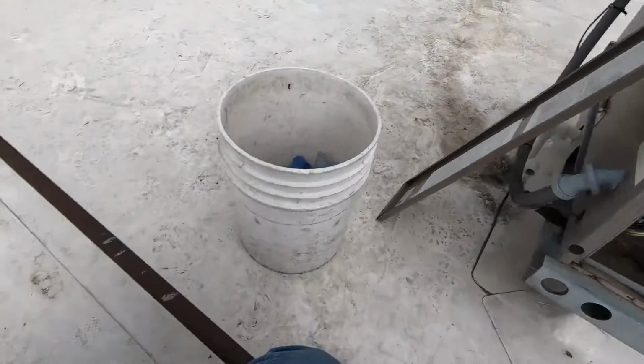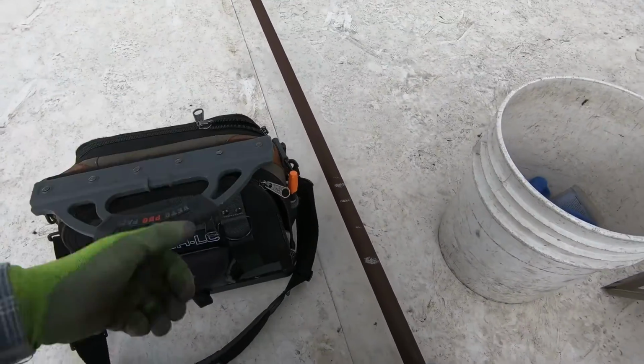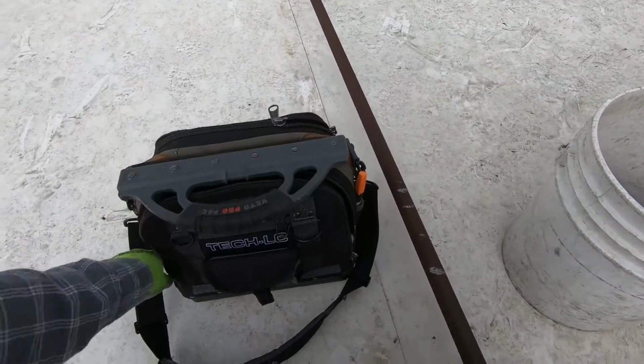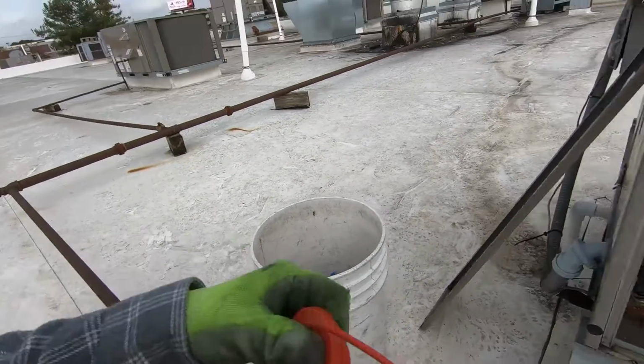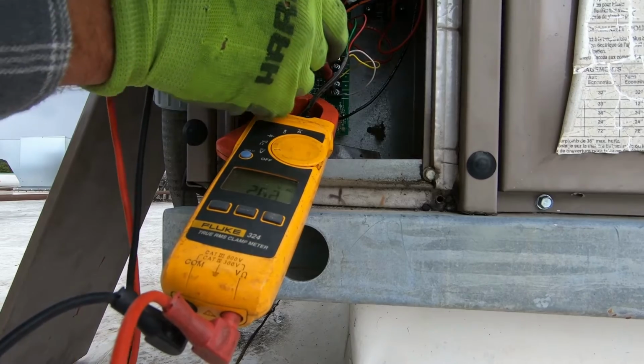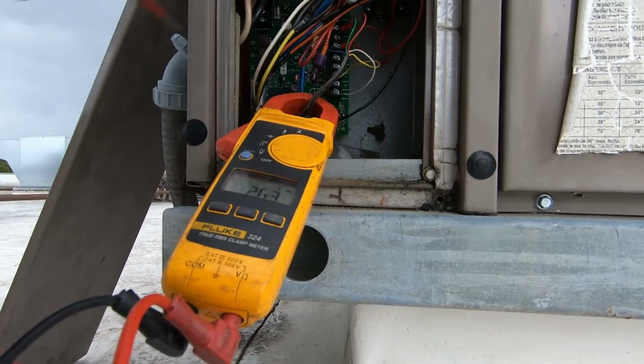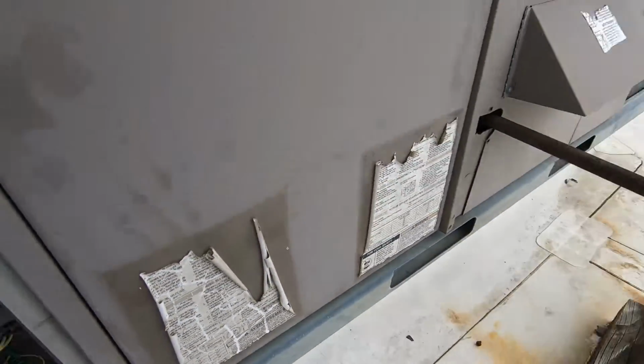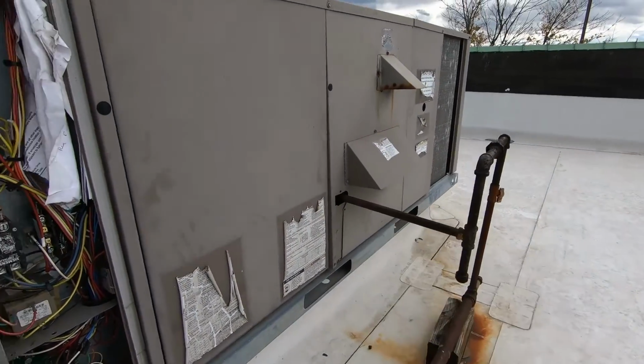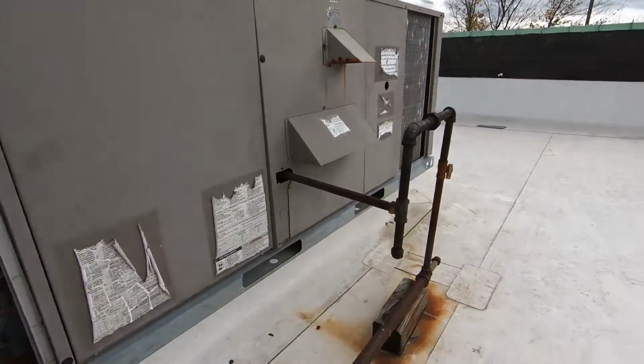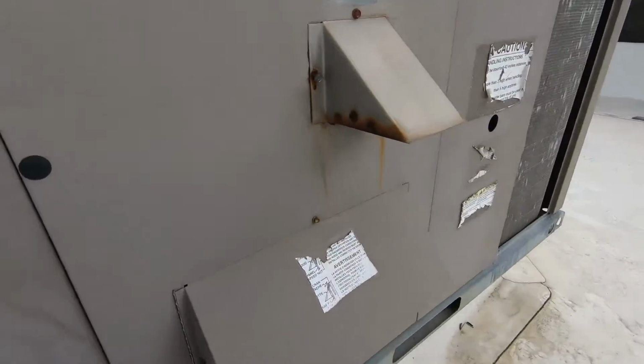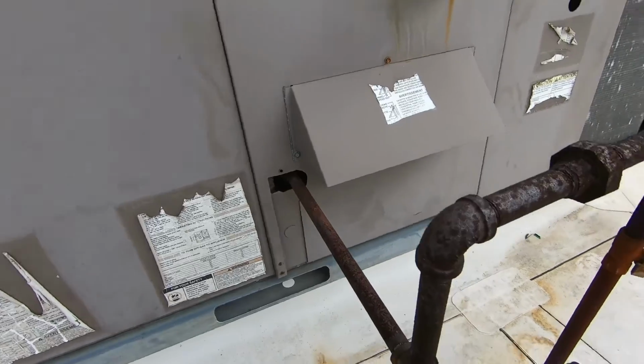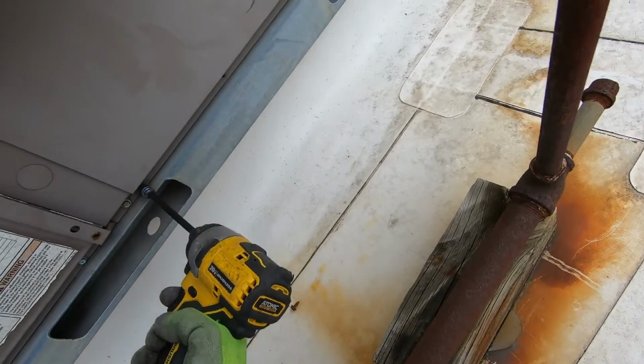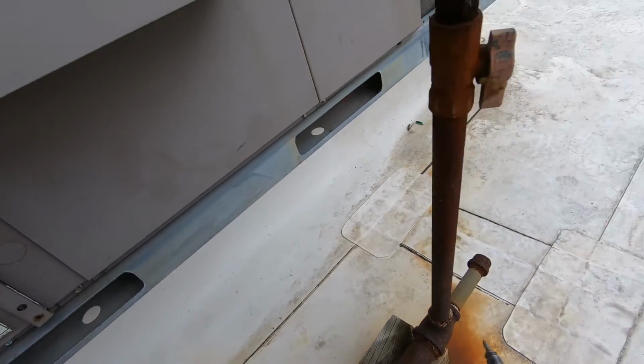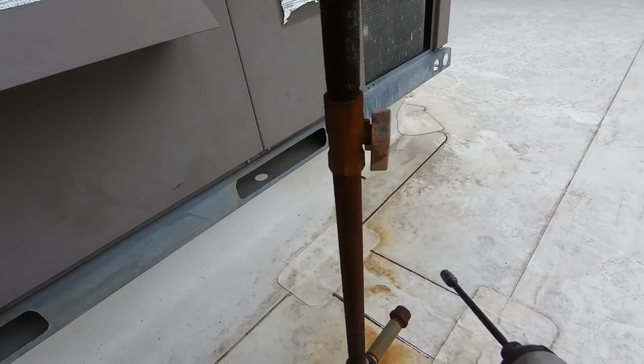All right, so I'm going to confirm that I do have a call, but I'm assuming we do since we've got a lockout code. All right, that's 26 volts at W. So I'm going to move on over here, get the heating section opened up, check to see if our limit switch is open. I believe these have that little resettable limit switch. Possible that that's tripped.